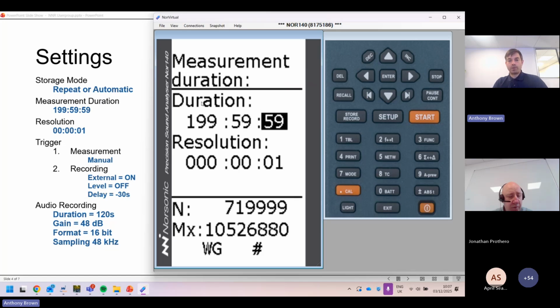This is about how long the meter will run for. You need it to run for at least 199 hours, 59 minutes, 59 seconds. Use the arrows up and down to go across, and then you can type over the number. Type in 59 and press enter. You'll see there's an E at the bottom when you've not yet entered the value; type in 59 and press enter if that comes up. Then you've got the resolution here, and you need to make sure this is set to 1 second. All that means is the duration it will run for is 199 hours, which is about a week. The resolution is the little dots on the graph, so it's logging the decibel level every 1 second, so you can see that nice graph when you download it. Have that set as 1 second, and when you're happy with that, press the enter key to go back to the setup menu.